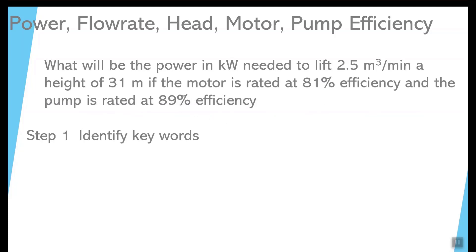Now let's take a look at the example question. What will be the power in kilowatts — notice, in kilowatts, not horsepower — needed to lift 2.5 cubic meters per minute a height of 31 meters, if the motor is rated at 81% efficiency and the pump is rated at 89% efficiency? The flow rate is 2.5 cubic meters per minute, which is not the required unit of liters per second, so a conversion will have to be done.